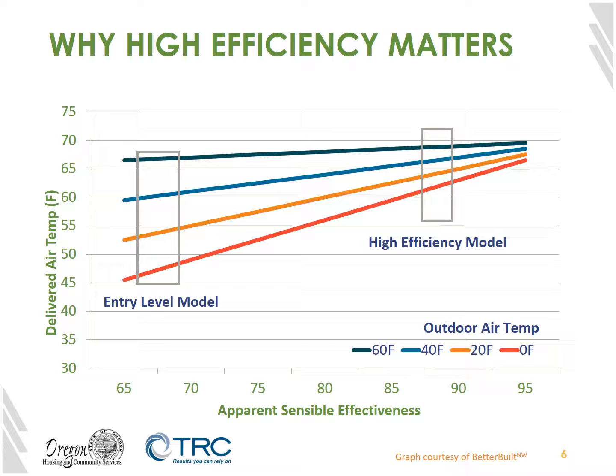It's important to note the difference between these two because we're going to look at the delivered air temperature at different outdoor temperatures. If we take a 20-degree outdoor temperature, that is the orange line, or the second line from the bottom that's going diagonally. If the outdoor temperature is 20 degrees, with the entry-level model, the air being brought into the building is going to be around 53 degrees. So when it's really cold out in winter, you'll bring in 53-degree air. That's still not bad, and it's much better than bringing in 20-degree air. But compare that to the high effectiveness model, the high ASE model. At that same 20 degrees, it's bringing in 64-degree air from the outside.